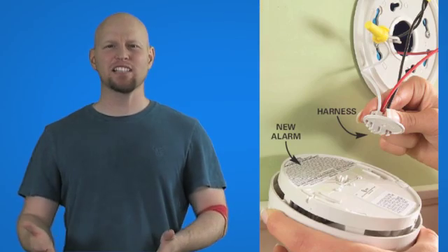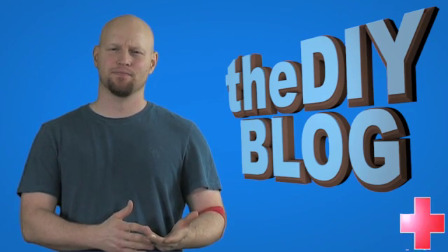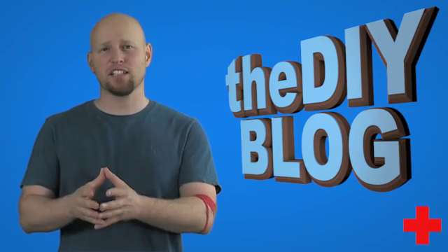If a chirping sound is heard from an individual smoke alarm, the battery should be replaced immediately. The battery should never be disconnected from the alarm for any length of time greater than the time it takes to replace it. If replacing the battery does not fix the situation, replace the smoke alarm with one of the same model number, then test the system to make sure the devices are interconnected properly and all go off when one goes off.